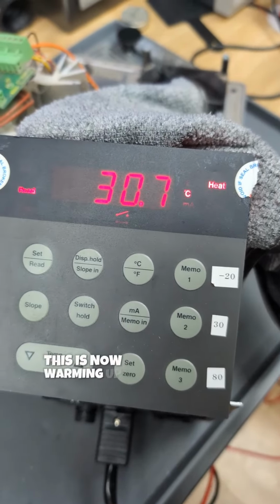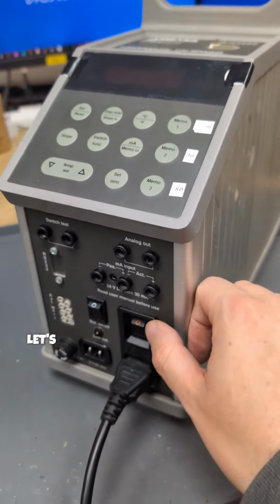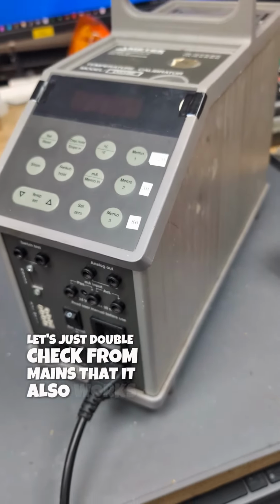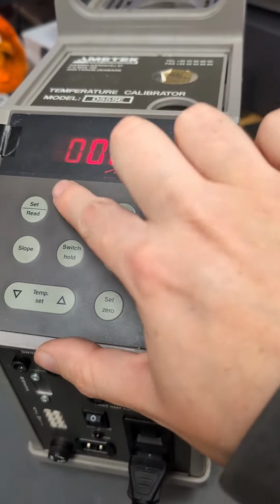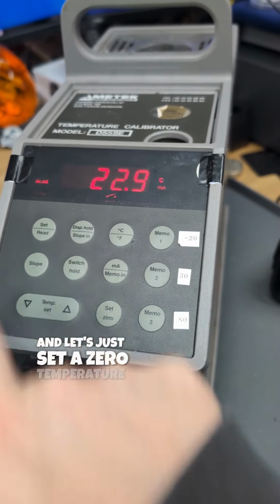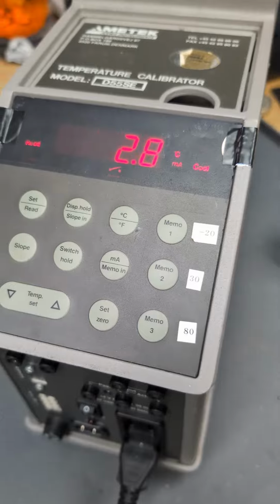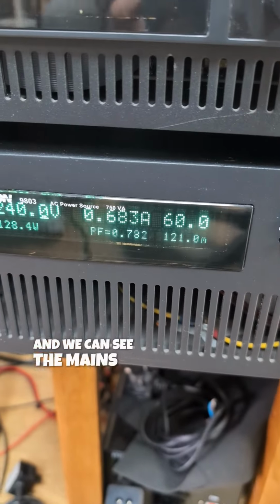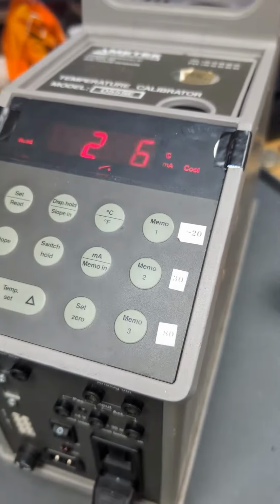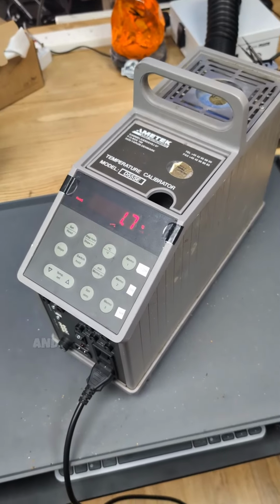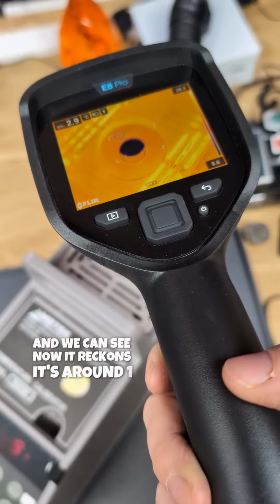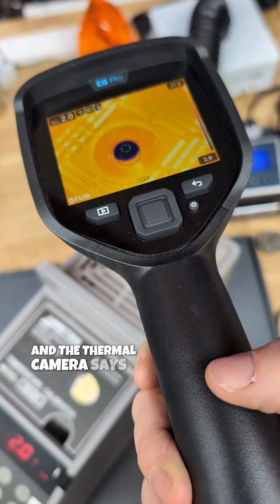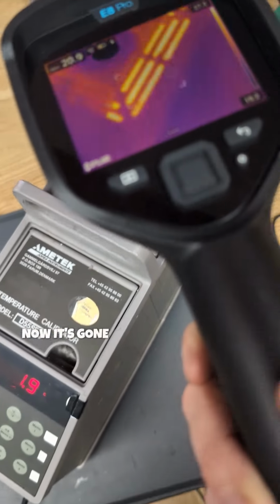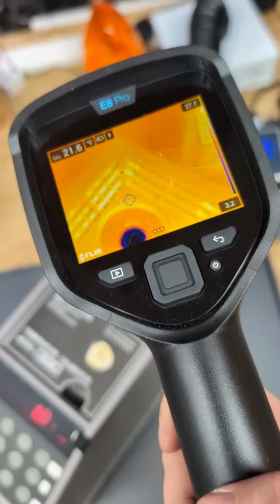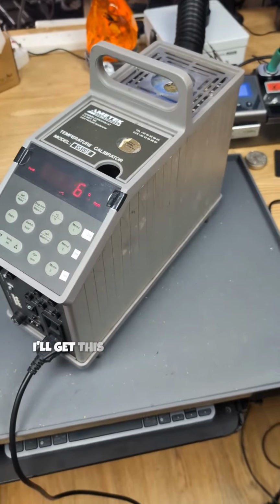This is now warming up and fully reassembled. Let's just double check from mains that it also works. And let's just set 0 temperature again. And we can see the mains is now pulling an extra half amp as well. This is cooling down. And we can see now it reckons it's around 1 degree. And the thermal camera says 2 degrees, so about the same. 2 degrees versus, oh yeah, 2 degrees now it's gone up to. So it seems accurate as well. So that does look like it's fixed. I'll get this one back to the customer.